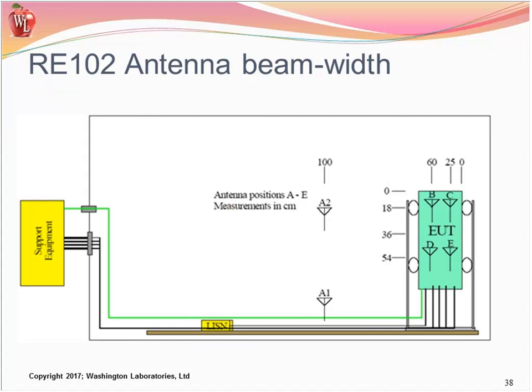The antenna beam width is not new, but I wanted to point out that the beam width is based on positioning the antenna so you're seeing the EUT and, depending on the frequency range, certain portions of the cable. This example shows the positioning, how we may lay out an item. So the antenna position is directly opposite that point on the chart where we say that item C is an antenna position for selected polarization / beam width calibration.